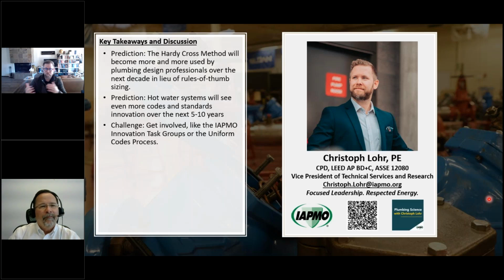So it's not necessarily saying one valve over another type, but it's to be very mindful of that in your system. If you're going to work in a healthcare facility with a lot of loops and a lot of changes, that could add a lot of cost to renovation projects, because you really have to go through and modify every single balancing valve in the system anytime you touch or modify the hot water return system. As opposed to an automatic balancing valve, as long as your piping has capacity and your pump has capacity, the system will figure itself out, in essence.